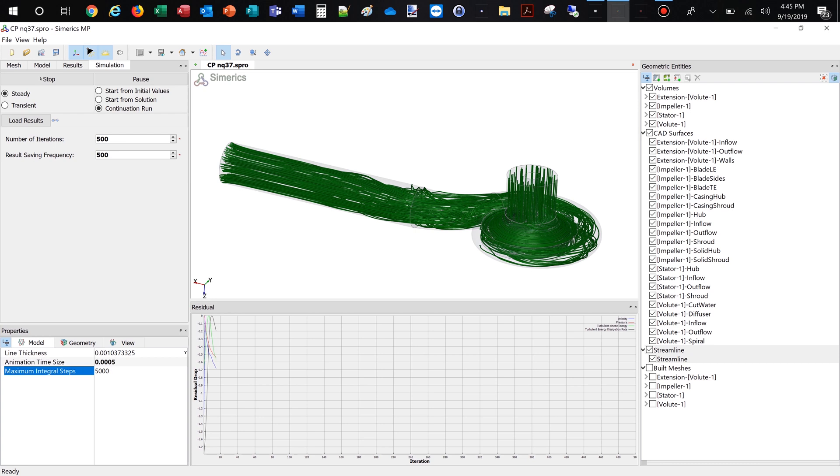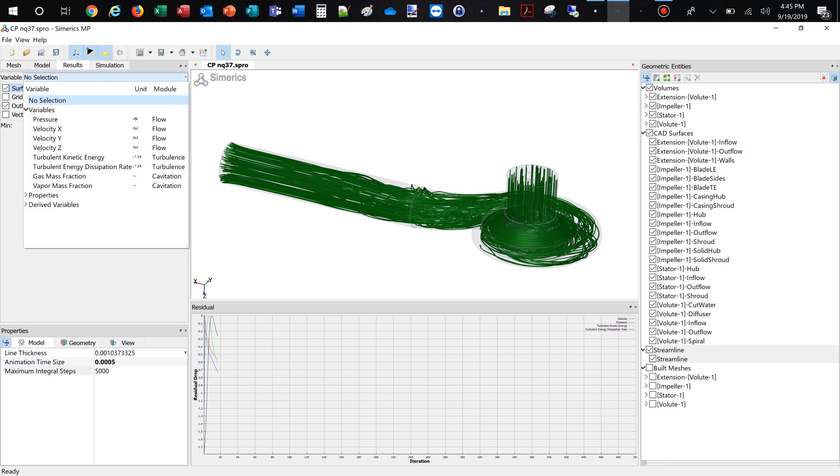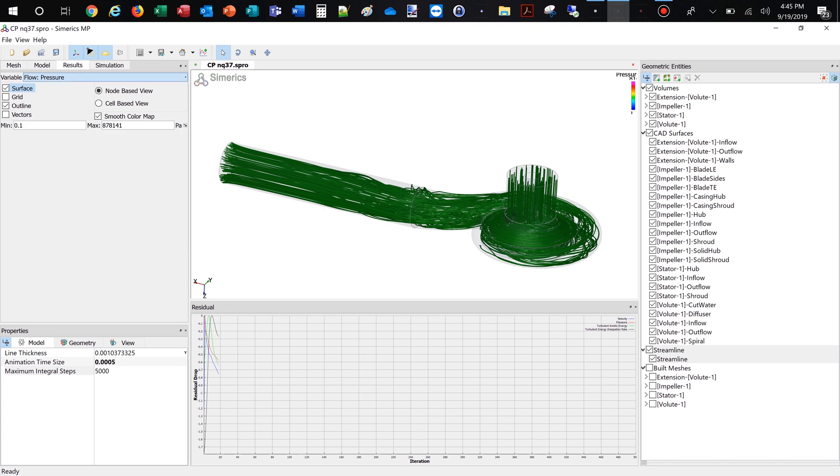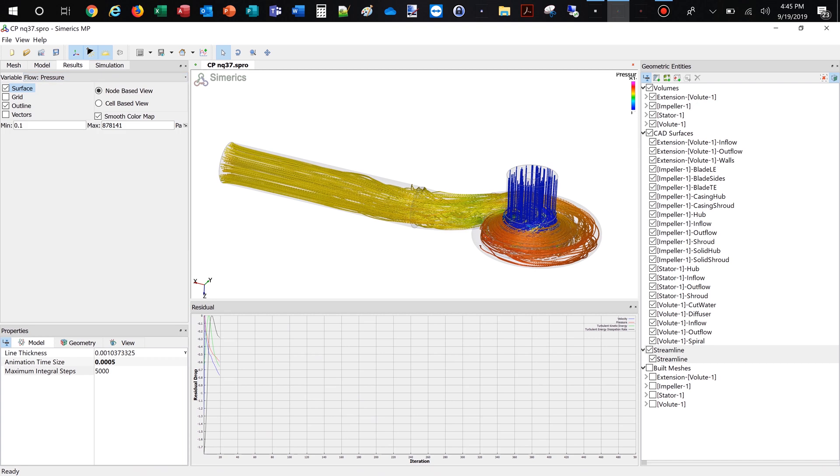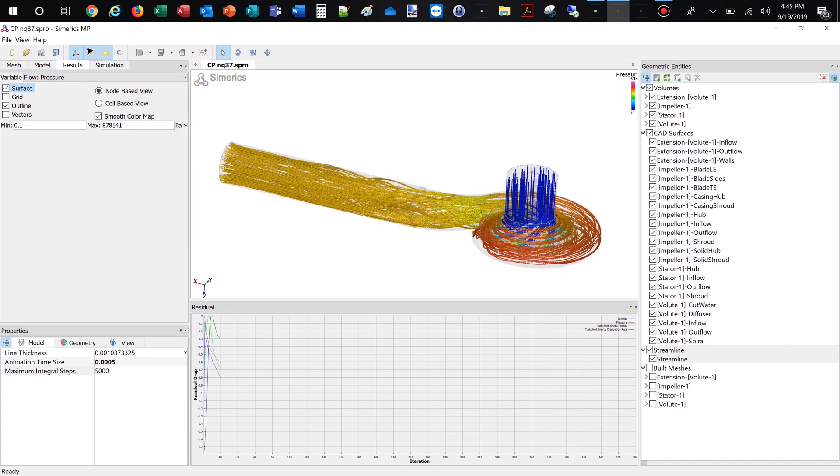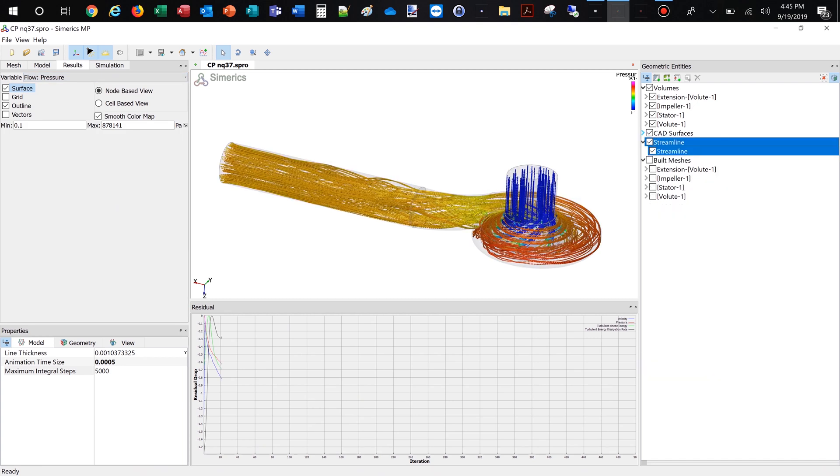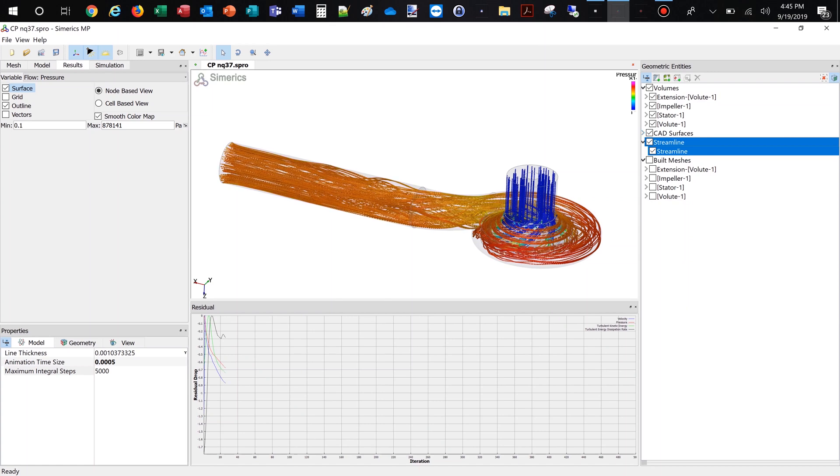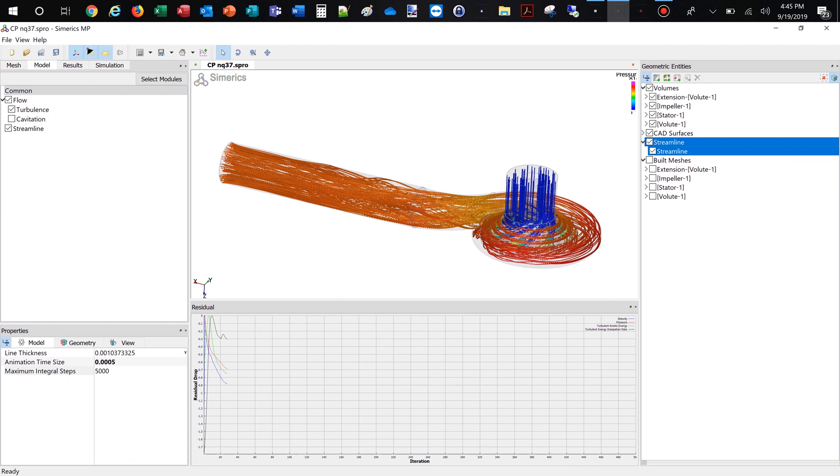Besides residuals, we can observe the flow field in real-time. Additionally, we are able to monitor physical properties and integral values like head rise of impeller and stage, hydraulic efficiency of impeller and stage, shaft power, and torque.